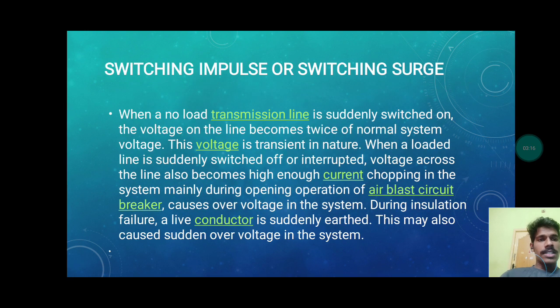And next one is switching impulses or switching surge. When a no-load transmission line is suddenly switched on, the voltage on the line becomes twice the normal system voltage. This voltage is transient in nature. When a loaded line is suddenly switched off or interrupted, the voltage across the line is also high enough, with current chopping in the system. Mainly the opening operation of air blast circuit breakers causes over voltages in the systems. During insulation failure, a live conductor is suddenly earthed. This may also cause sudden over voltages in the system.